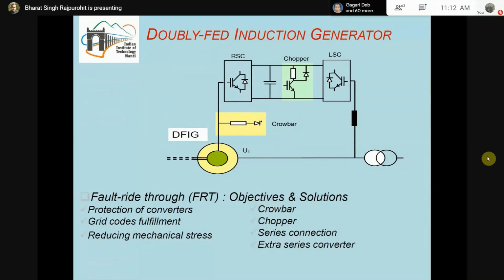This rotor side converter, by utilizing the DC link capacitor, is able to inject the reactive power required by the doubly fed induction generator, and hence this DFIG doesn't want any reactive power from the grid side. All of its reactive power requirement is met by the rotor side converter. If the grid wants reactive power, the rotor side converter can even inject more reactive power, which can then transfer from rotor to the air gap and air gap to the stator, and be fed to the grid. So it means that by utilizing control of the rotor side converter, the DFIG can be made a zero reactive power exchange with the point of common coupling, and even beyond that it can provide reactive power support to the grid also. Similarly, it can absorb reactive power based on the requirement also. So this is how the reactive power requirement can be obtained by operating the rotor side converter. Fine. The rating of this rotor side converter should be appropriate to incorporate these control functions.